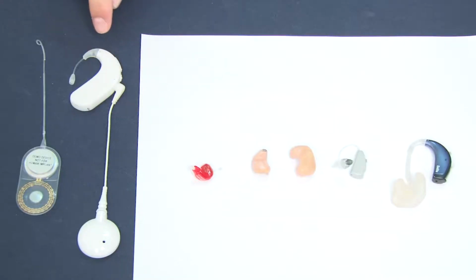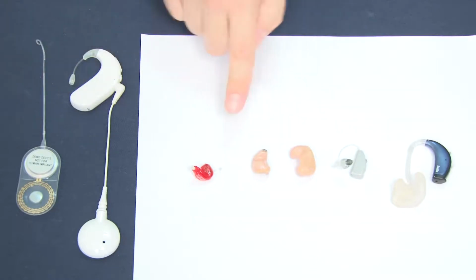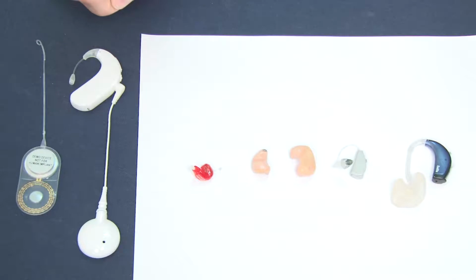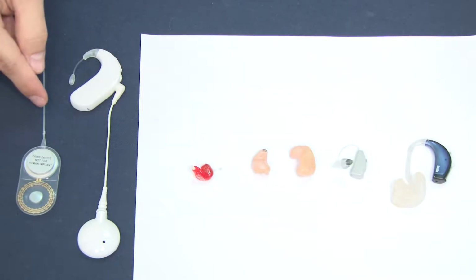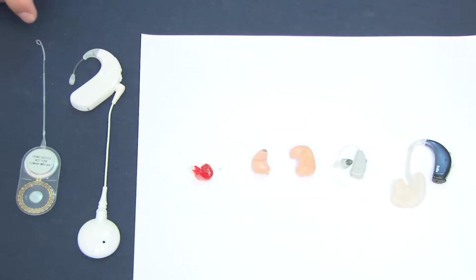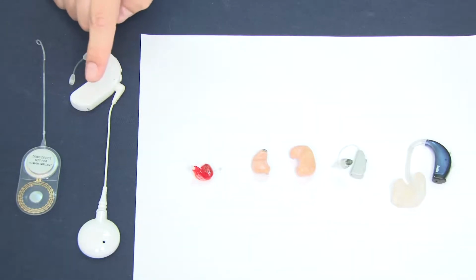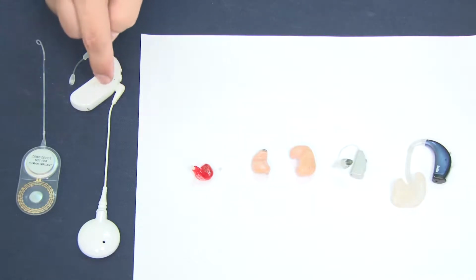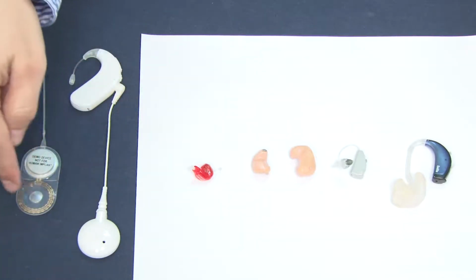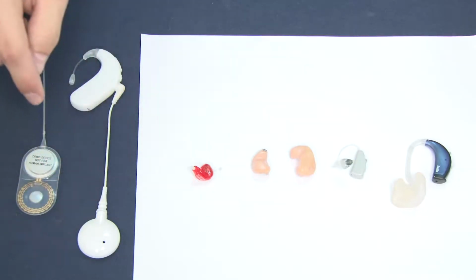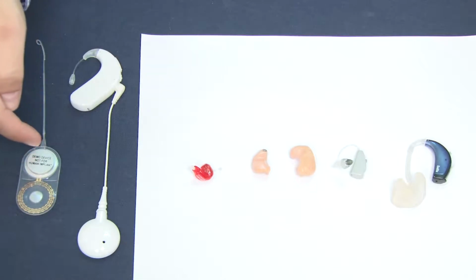And now we'll move on to cochlear implants. As you can see, it's much larger than the BTEs and the ITEs we have right here. A cochlear implant is a surgically implanted device with this piece here being implanted under the individual's skin and this electrode array being inserted directly into the cochlea. The main parts of a cochlear implant would be your microphones here on the back that pick up your environmental sounds. You also have your speech processor here, which picks out speech sounds from background noise. And you also have your transmitter right here. And then you have your receiver that is implanted on the inside. So the transmitter sends signals to the receiver, which in turn sends those electrical signals down to the electrode array to directly stimulate the cochlea.